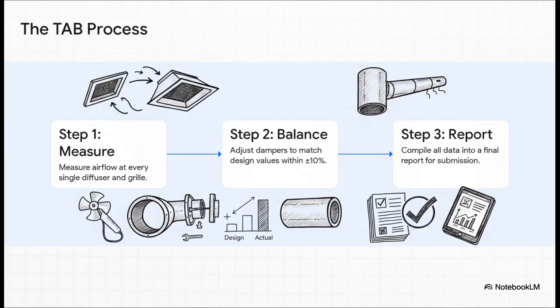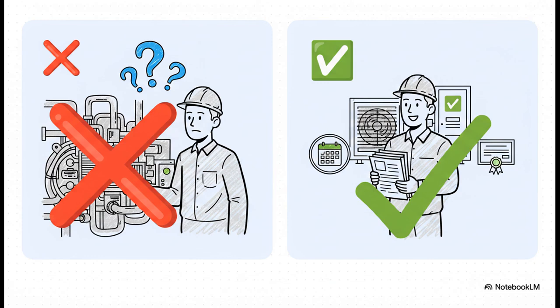So what is this TAB process? It's actually really simple in concept. A specialized team comes in and measures the actual airflow coming out of every single vent. Then, they tweak the dampers and the ducts until the real-world airflow matches your design drawings, usually within about 10%. All that data gets compiled into a big report that proves your system does what you said it would do. And remember, your work isn't over when the system is turned on. You're not just leaving, you're handing over a valuable asset. That means you have to provide the complete operations and maintenance manuals, a detailed schedule for future preventative maintenance, and proof that you've trained the building staff on how to use it.